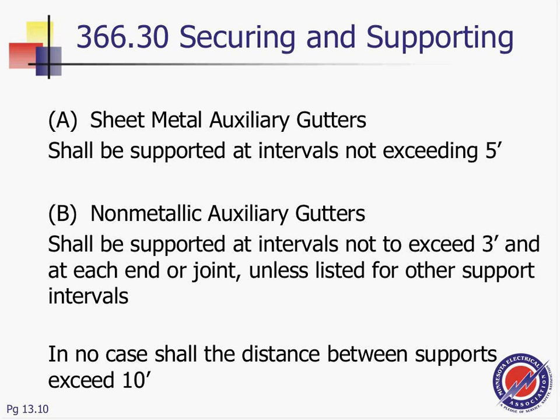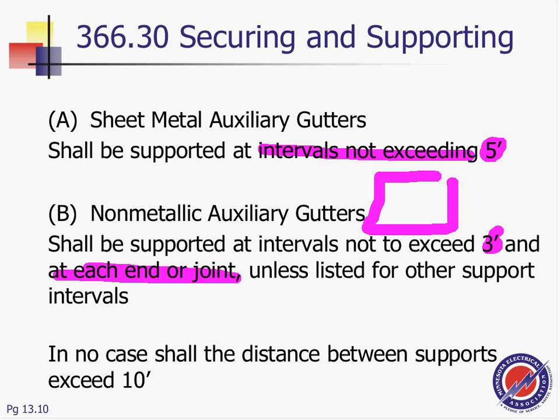Sheet metal raceways, guys, shall be supported at intervals not exceeding 5 feet, non-metallic 3 feet, no problem, and at each end. So at each end and every 3 feet. So here's my box. At each end, support; 3 feet, no support needed; 3 feet here, support at ends. If I have a box over here, 3 feet support, and after that, 3 feet support.